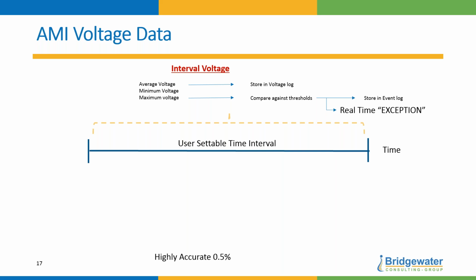So this notion of interval voltage, you can give it any kind of interval, 10 minutes, an hour, whatever it is, you set it. What does it do during that time? Again, it depends upon the vendor, but many meters give you the average voltage over that interval and the minimum and maximum during that interval. What's the min? That's the 1 second or 5 second, whatever it is. So you can set up the meter and then store those values in a log. If it's an hour, every hour it'll store max, min, and the average during the hour. You're going to put up thresholds, and if it exceeds those thresholds at the end of the hour, it'll store it in a log, and the meter can send out an exception to say, ooh, I went past the threshold. That's your typical interval voltage.